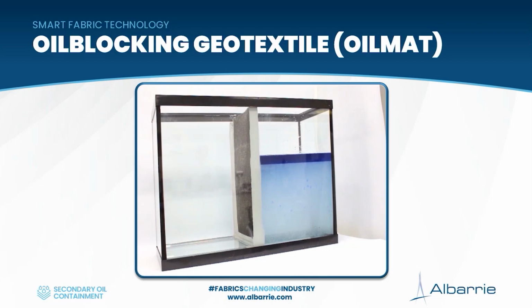Imagine you have a containment system using this material installed, and there's an event where it's raining at the same time as a catastrophic equipment failure. Both things fill into the containment, giving you a mixture of oil and water. The higher concentration of oil rises to the top, while the water continues evacuating the containment system through the floor. Small trace amounts of oil get captured within the mat itself, so the liquid passing through the floor and coming out the other side is clean and meets the minimum discharge requirements set out in North America.